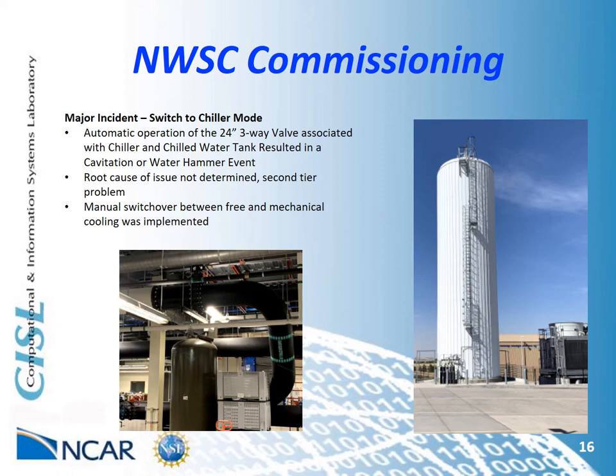The root cause of the problem was not determined specifically. Hindsight tells us we should have, but the demands of the schedule during commissioning caused it to become a second-tier problem. In any case, the team was now aware and concerned that there could be issues with the transition between the two cooling modes that could cause damage within the plant. Manual switchovers between the modes had been accomplished with no issues resulting, and it was determined that a manual switchover mode should be explored and implemented.